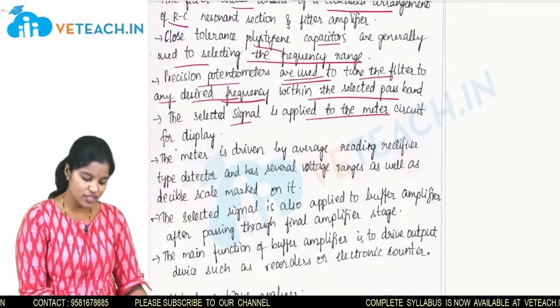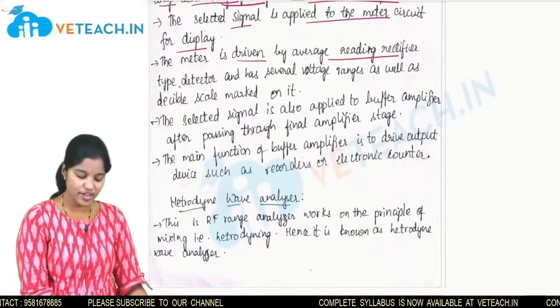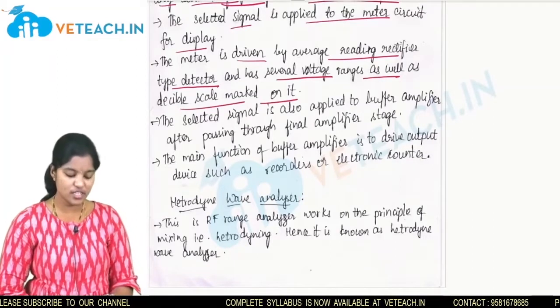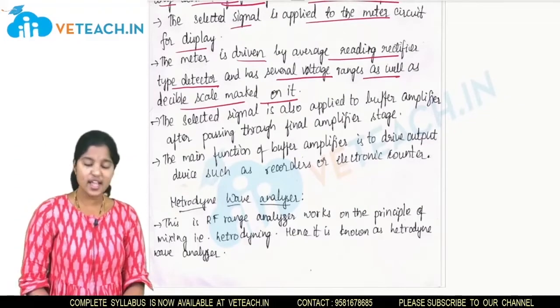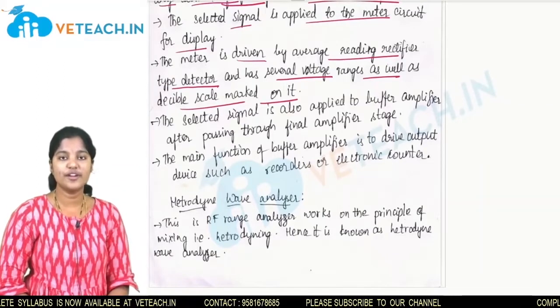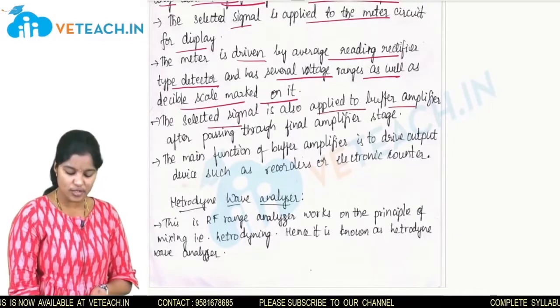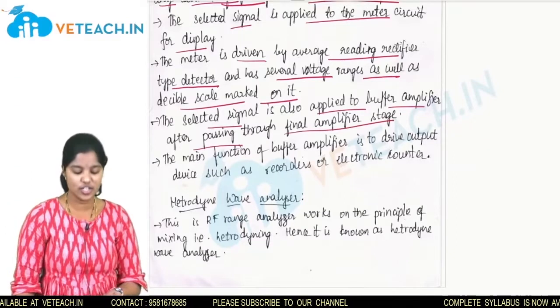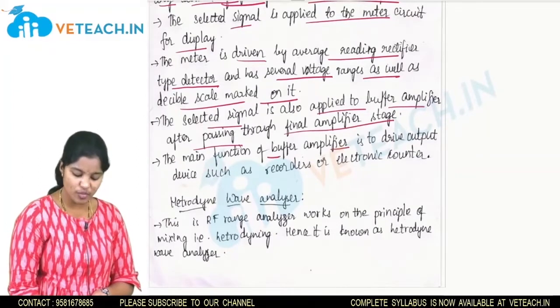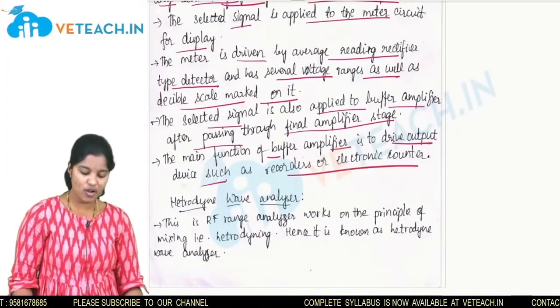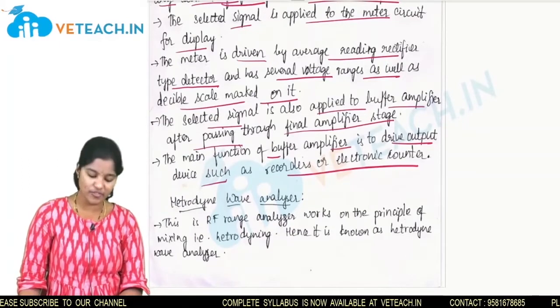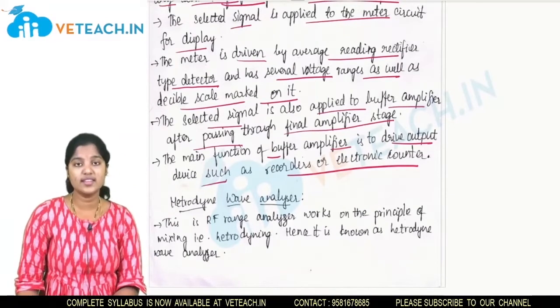The selected signal is applied to the meter circuit for display. The meter is driven by an average reading rectifier-type detector and has several voltage ranges as well as the desired scale markings. The selected signal is also applied to the buffer amplifier and passes through the final amplifying stage. The main function of the buffer amplifier is to drive output devices such as recorders or electronic counters.